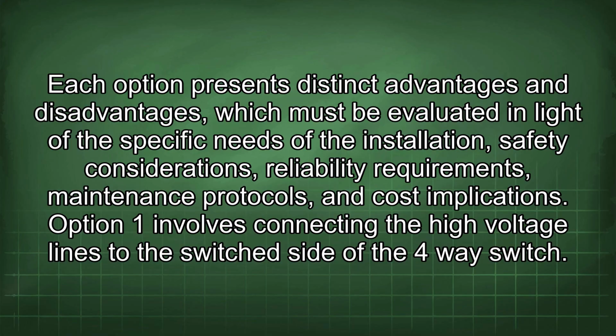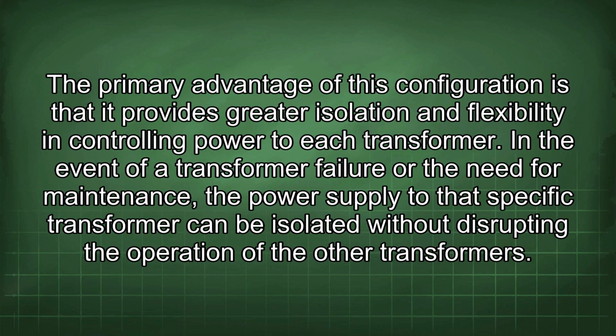Option 1 involves connecting the high-voltage lines to the switched side of the 4-way switch. The primary advantage of this configuration is that it provides greater isolation and flexibility in controlling power to each transformer. In the event of a transformer failure or the need for maintenance, the power supply to that specific transformer can be isolated without disrupting the operation of the other transformers.